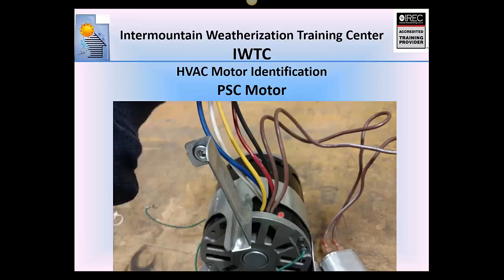Here's a picture of a PSC motor showing all the leads. There's the capacitor with two wires — brown and brown-and-white. There are four speed leads: black, red, yellow, blue, plus a common lead and a ground. Typically black is low, red is high, yellow is medium-low, and blue is medium-high.